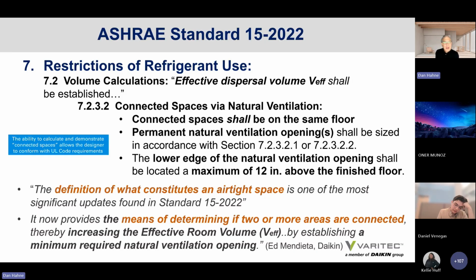Section 7 actually assigns a procedure and method for calculating volume of refrigerant that may be released into a space, of a volume of an A1 or an A2L refrigerant that can be released into a space. Effective dispersal volume is a term used throughout the standard. It is the cubic volume of space in the occupied space of a building or a room that is served by a variable refrigerant system. To expand the cubic volume of space, ASHRAE assigns a connected space level where natural ventilation can flow between connected spaces through vents and other listings as prescribed by the standard.